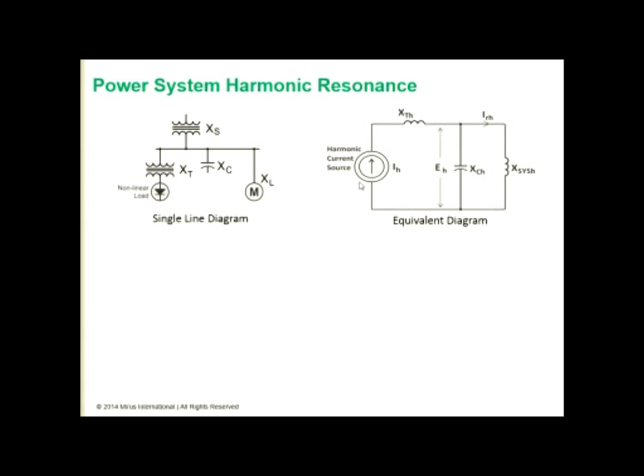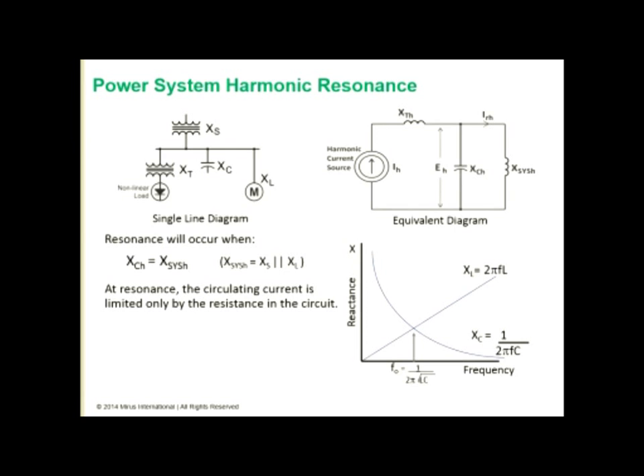And here we've got a harmonic current source injecting harmonics into the power system. These harmonic currents pass through the source impedance, the transformer impedance, and then they pass through the combination of the parallel capacitance and the inductance of the system. And the inductance of the system is also a parallel combination of the loads, the other loads, and the power system reactance. Resonance will occur where the inductive graph line crosses the capacitive line. And at this point, our resonance frequency is going to be 1 over 2 pi root LC.